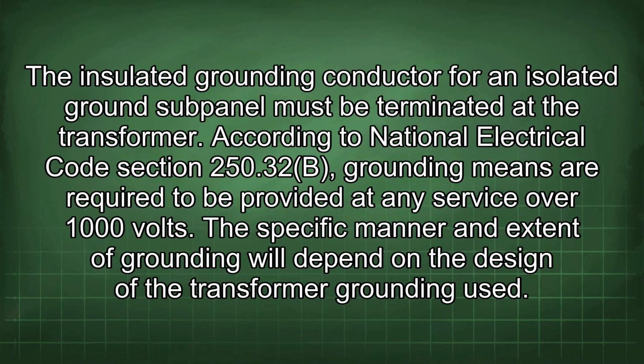The insulated grounding conductor for an isolated ground subpanel must be terminated at the transformer. According to National Electrical Code Section 250.32(B), grounding means are required to be provided at any service over 1000 volts. The specific manner and extent of grounding will depend on the design of the transformer grounding used.